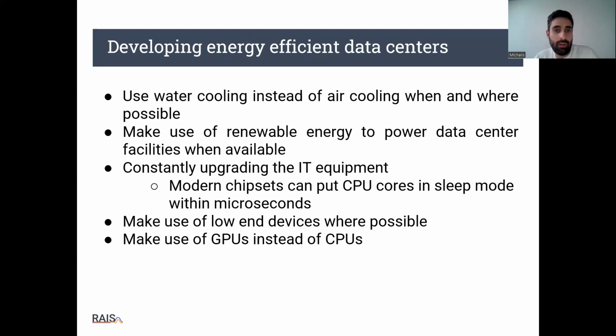In order to develop more energy efficient data centers, some approaches are detailed here. One is to use water cooling instead of air cooling when and where possible. Water cooling is much more energy efficient and can support increased densities in data centers and compute-intensive applications, making it an ideal solution. On the other side, it is more expensive, and there is a danger of failures in the IT equipment in the event of leakage.